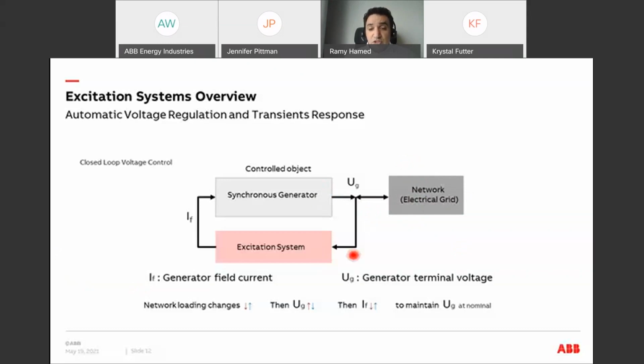So the excitation system is continuously measuring the voltage at the synchronous generator, and it will act immediately to change its output, which is the DC current going to the generator rotor, so that it can maintain the generator voltage at its nominal value.